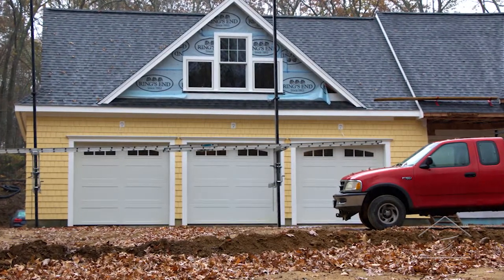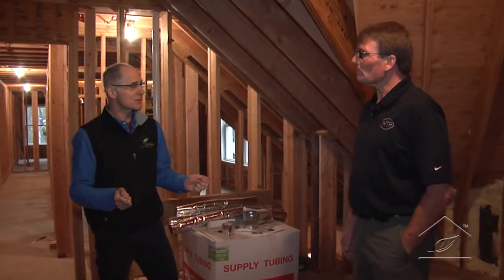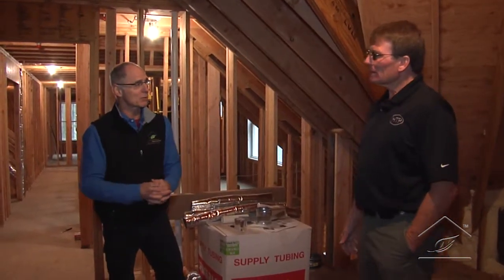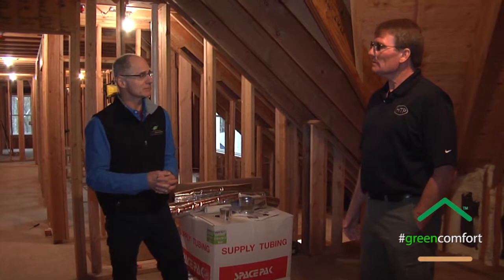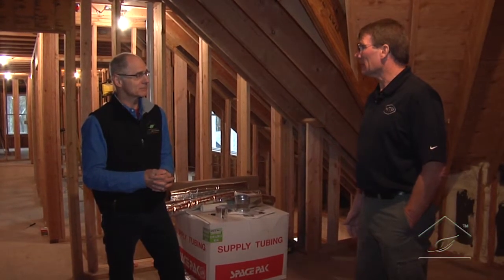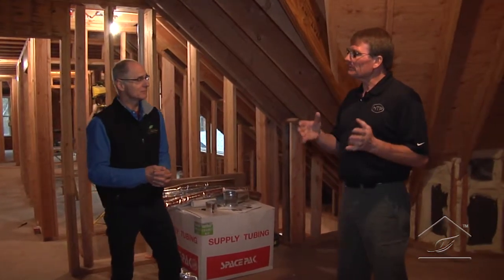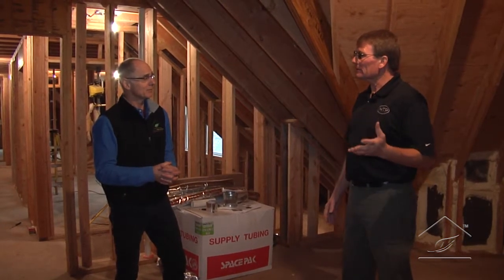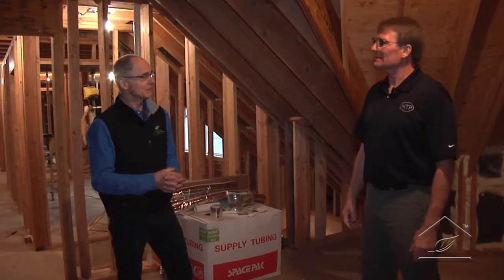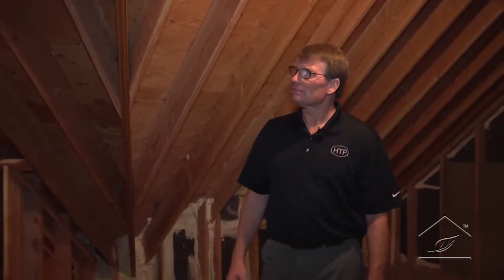Sorry, an afterthought. Walking through here, and mounting and schlepping and putting it on the roof. What makes more sense? Bigger few or more smaller? The larger collectors are a little bit more efficient for cost, of course, but it also depends on what your structure might be able to handle. You might have more of the smaller collectors, and common collectors are usually 4 foot by 6.5, or 8 foot, or 10 foot. If you've got a great open roof space that doesn't give you any impedance on area, less of the larger collectors would be a more economical direction to consider.